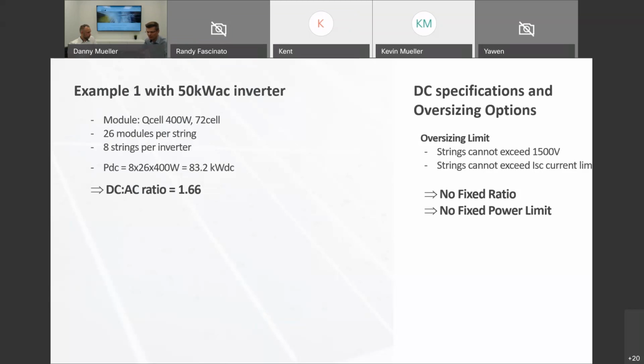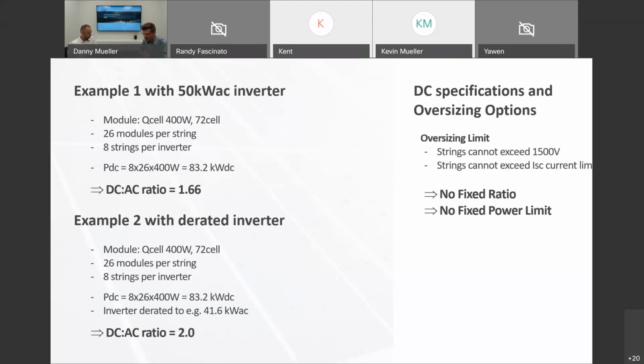So typically, even with a larger, higher wattage, or even the highest wattage panel, let's say a 430 or 440 even, and even bifacial types of those panels, will not typically exceed 15 amps ISC. So we can go to an even much higher DC to AC ratio out of the box. There is, however, a second option where you can also scale your DC to AC ratio, and that's for applications where the out-of-the-box 1.6 or 1.8 is not sufficient.